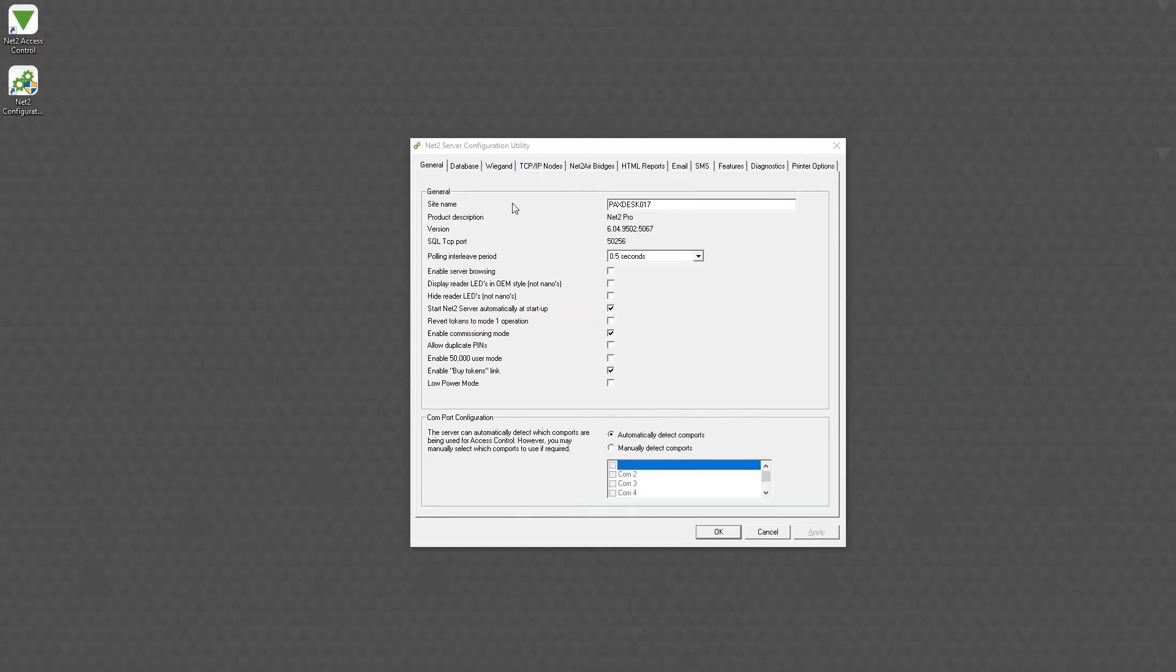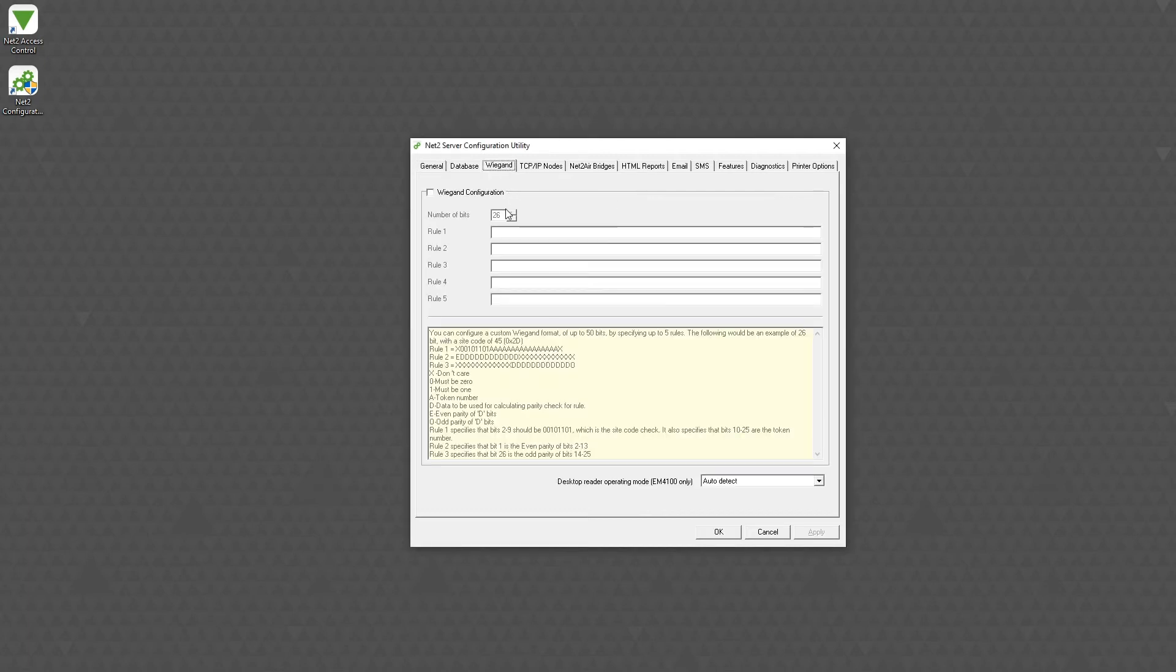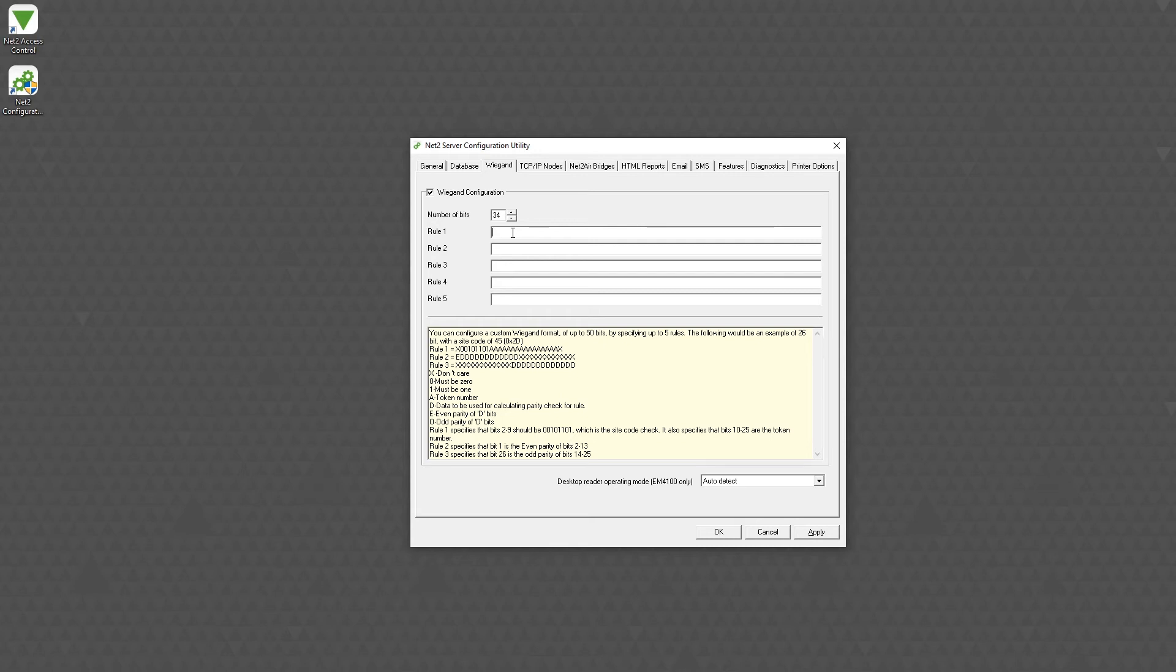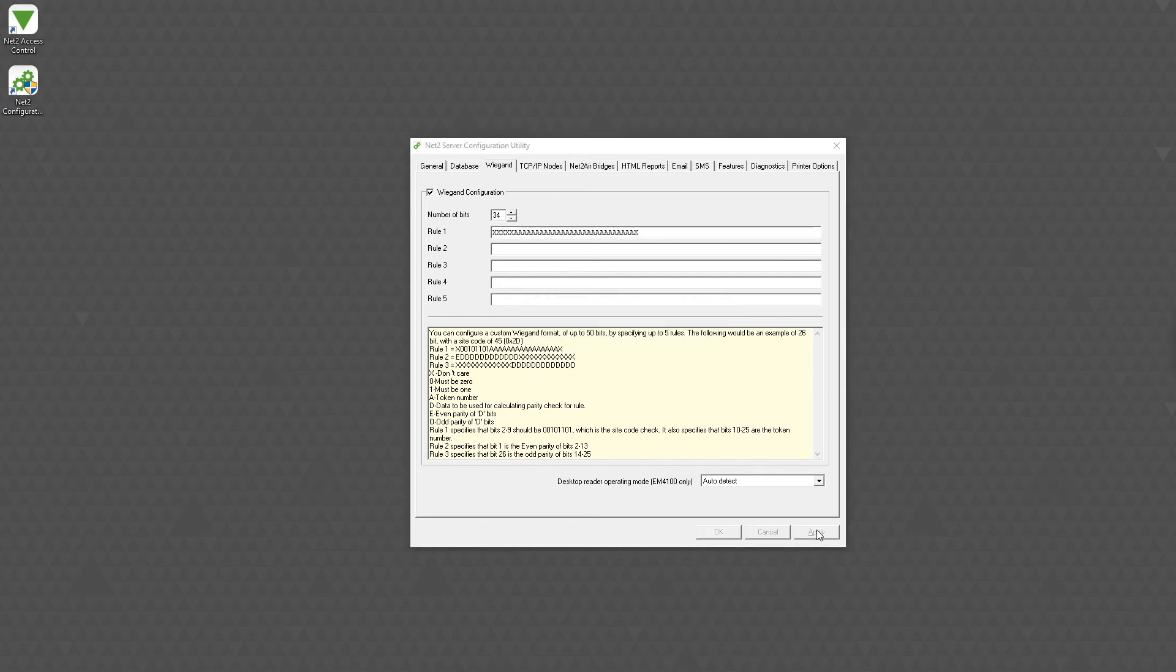A custom Wiegand rule will need to be set up in the NET2 configuration utility. Under the Wiegand tab, check Wiegand configuration. A new custom 34-bit rule needs to be entered using 5 x's, 28 a's, followed by 1 x at the end. By creating this rule, the reader will use the required section of information to provide the same card number as other NET2 Mifare readers on the system.